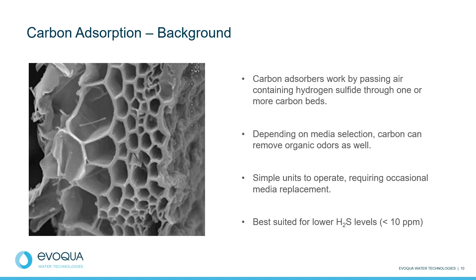Because the hydrogen sulfide concentration will impact how quickly that carbon gets spent and how quickly it needs to be replaced, we typically recommend using carbon systems for sulfide levels that average less than 10 ppm or so. Otherwise, the carbon just gets burnt through too quickly and you have to change the carbon out a lot quicker.